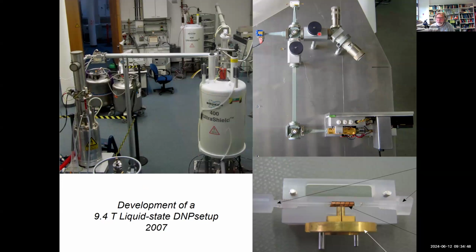It's a Michelson interferometric setup, so you can in principle even measure the EPR signal under the gyrotron microwave conditions, because you just make an interference for the EPR detector. And this is a home-built probe head: you see, the NMR frequency is the coil, EPR is the cylinder, yeah? And this is the waveguide for the EPR connection.